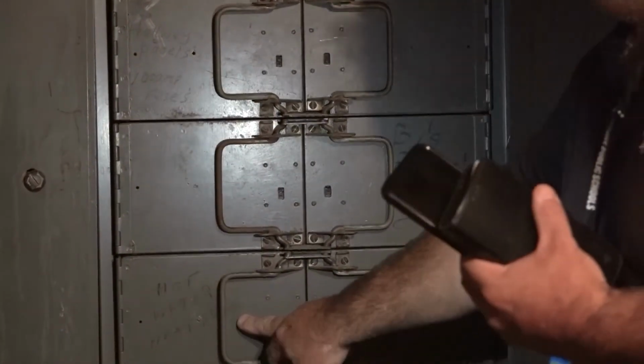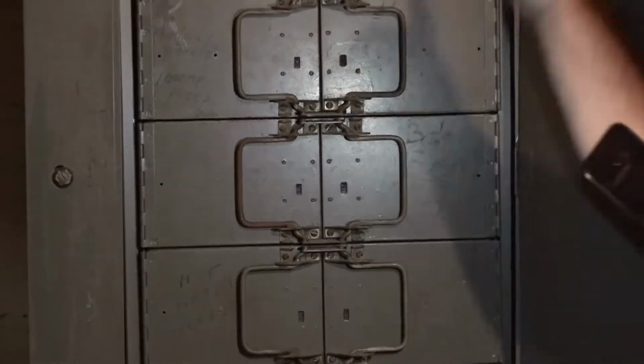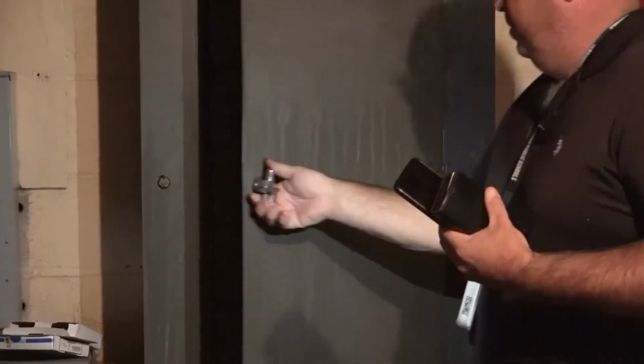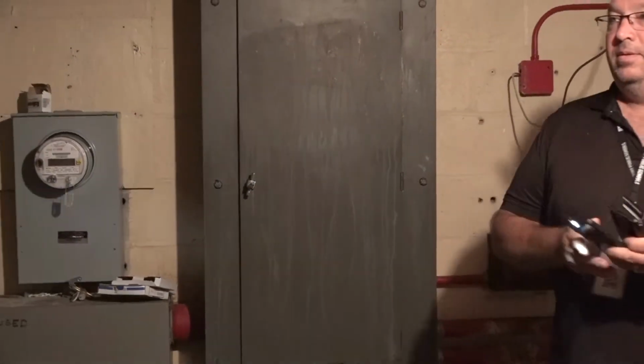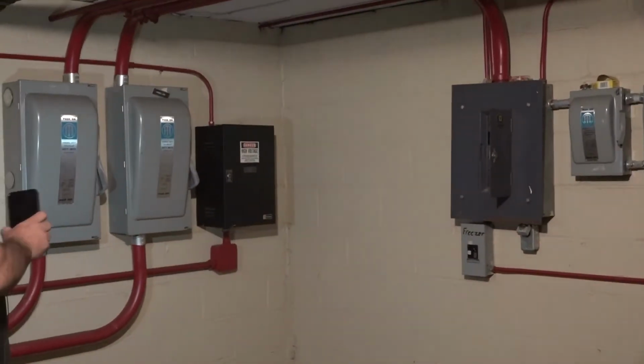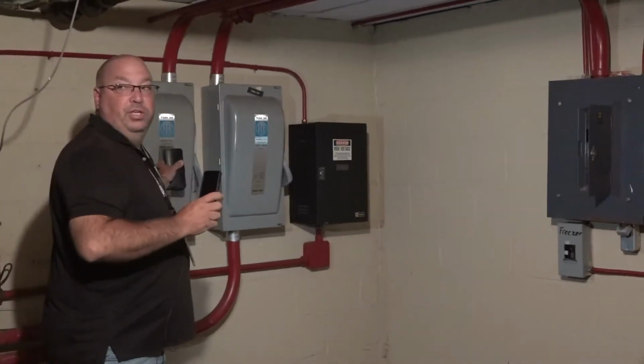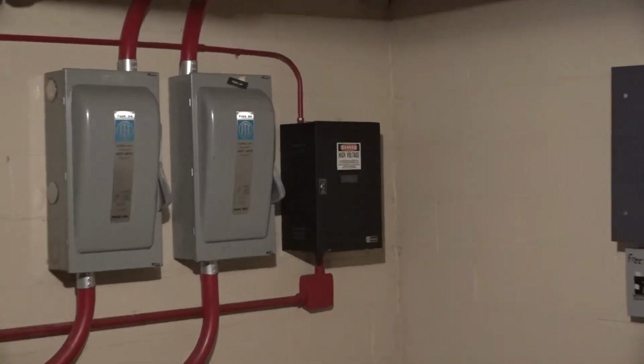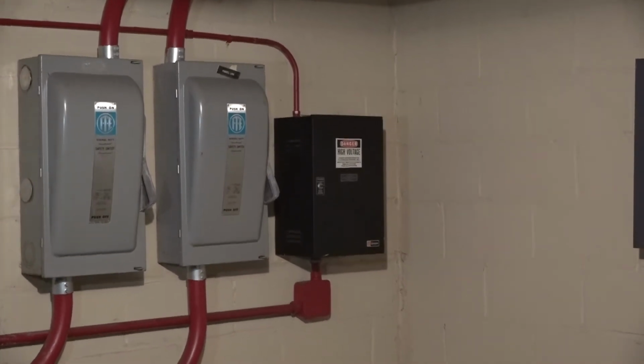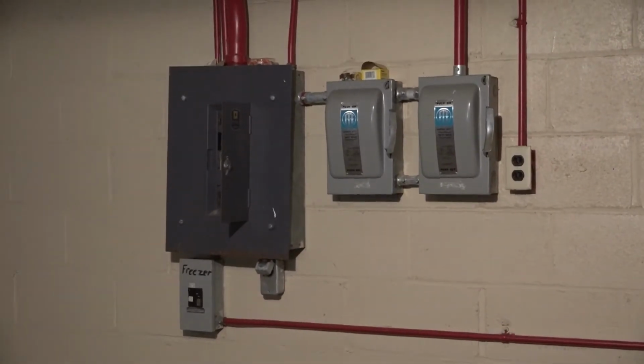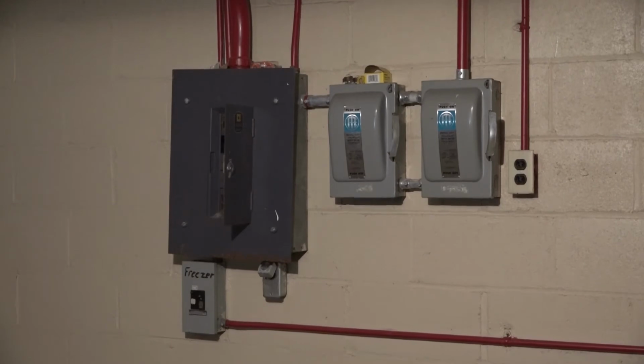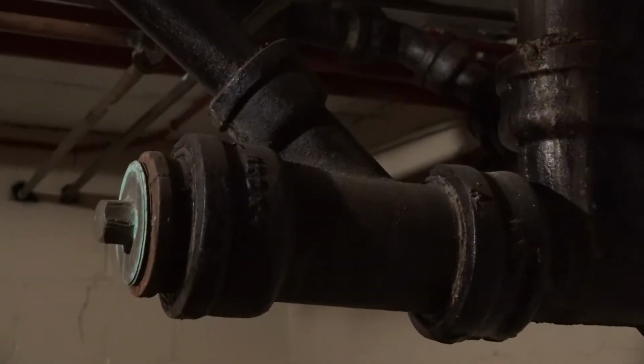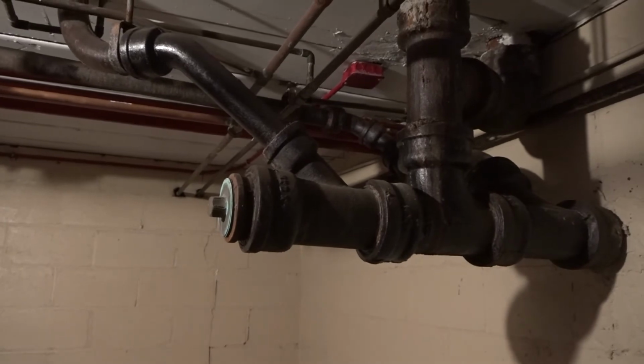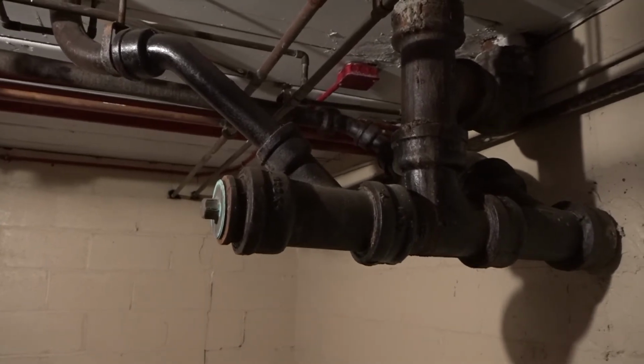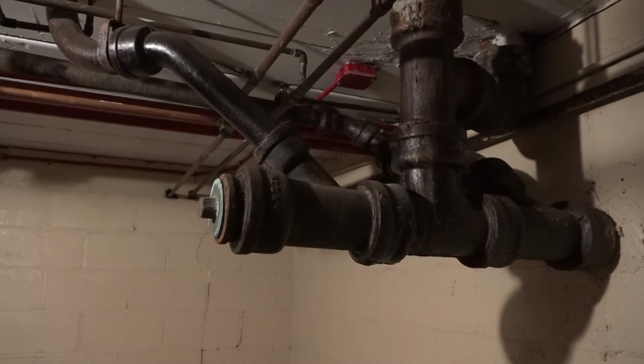And then this one's a water heater, and then these go to the panels in the hallways upstairs. Big version of your circuit breaker. Yeah, panels here and some disconnects. I think these are for the newer wings, the addition wings, those two there. That panel's for the kitchen. There is also a newer sub panel up in the kitchen as well, just because we ran out of power and had more, so there was a pile of block on the floor and stuff. But as far as power in these buildings, we're pretty much maxed out in here for power.